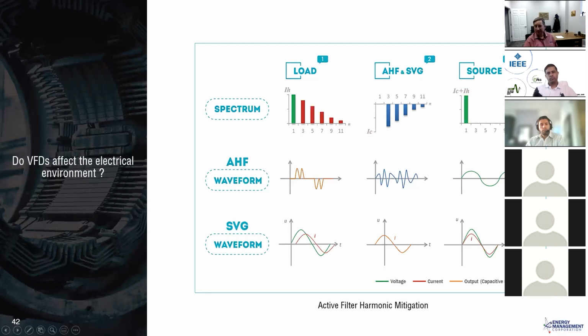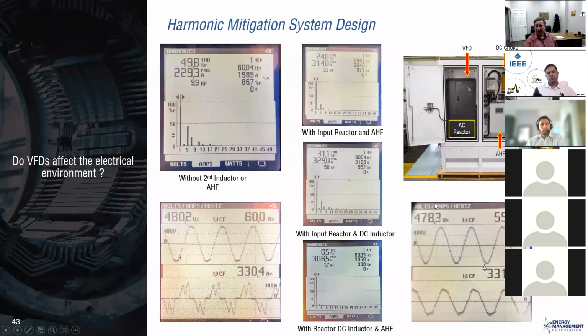Continuing on, this shows the outcome of the process we went through to determine the best way to make this system work. When we first put the system in our test lab, we have a generator, and we loaded it up to about 300 and some amps. We were getting 49%, almost 50% distortion, and that's with that harmonic filter. Now, granted, we have a weak power source, so that might have been worse than normal.